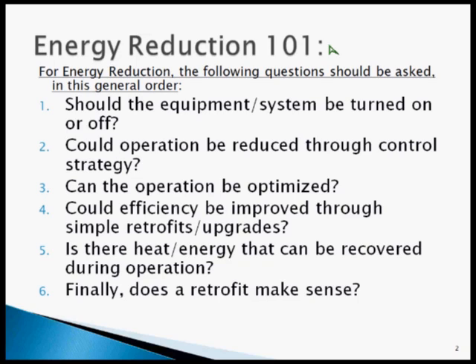Unfortunately, a lot of times equipment is sized too large. So maybe we can use controls to make it be smaller and make it respond, variable speed drives. Maybe we can alter the system that was too large. Now, a lot of times it isn't the engineer and architect's fault because people have done lighting retrofits. They've done window retrofits. The computers keep giving off less and less heat. So over time, the equipment maybe sized 10 years ago for something, that load just isn't there anymore.